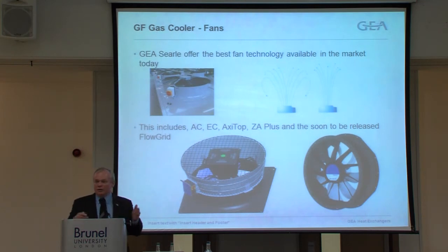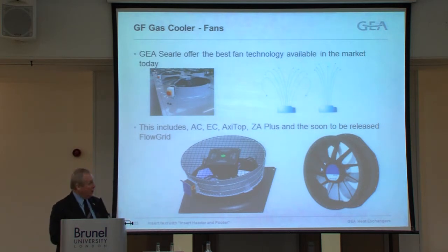Like the main unit, you've got loads of different modules. To go with those modules, we have different types of fans. We're using Ziehl-Abegg, EBM, we're using EC technology, we're using Axitop, the ZA pluses, and we're using Woods short case axial fans. You'll find that the characteristics of the fans are completely different. These are low pressure, high performance fans. If we can reduce the pressure drop that we impose on the fan, we're going to get substantially more air. So going for a very large module reduces the pressure drop, and then we use this type of fan. And I understand that Simon's just started a project on the flow grids. I'm sure he'll be able to answer your questions on that because I've got no idea what he's talking about.